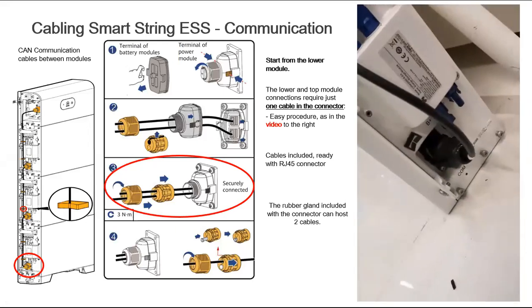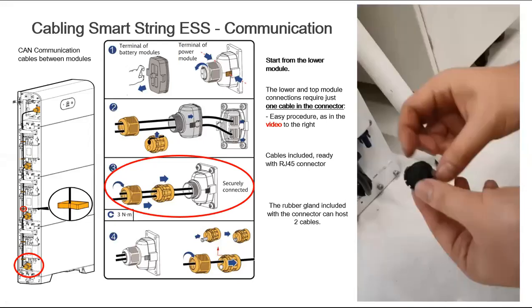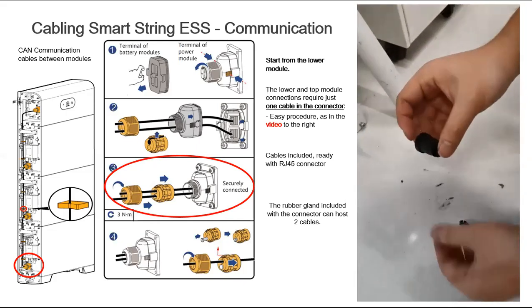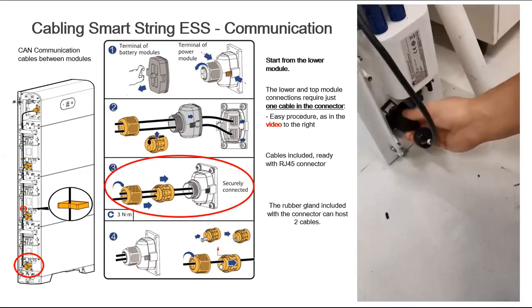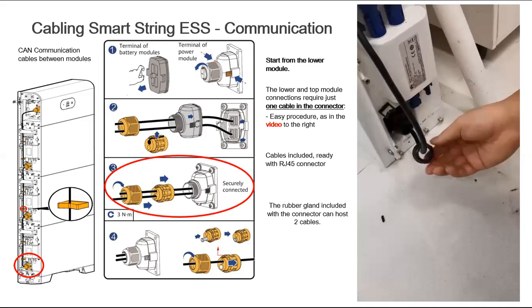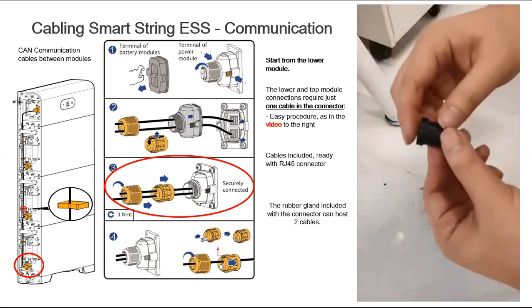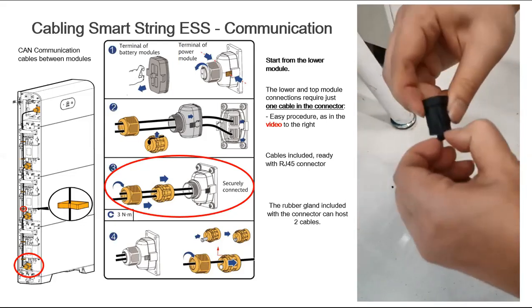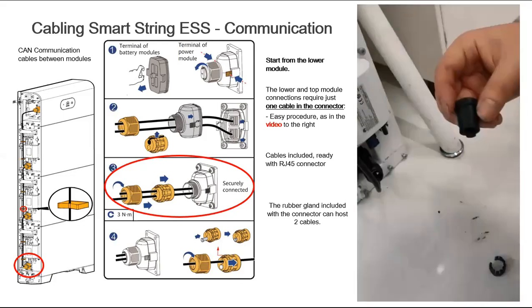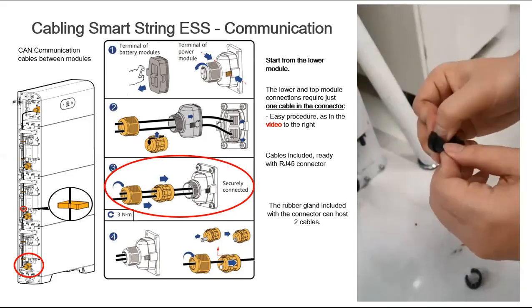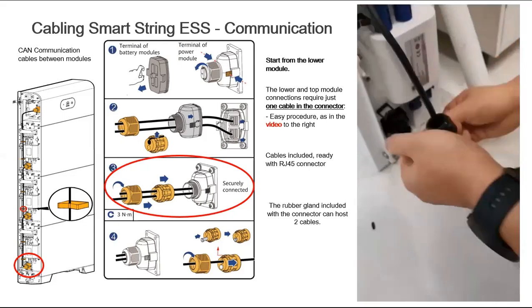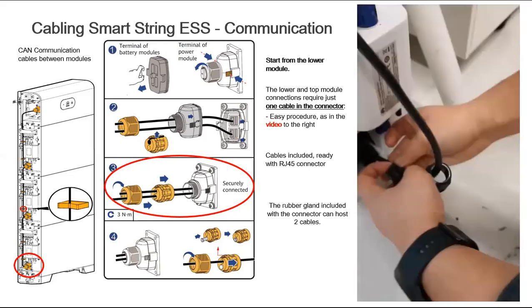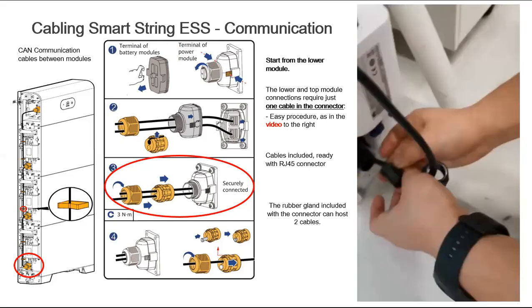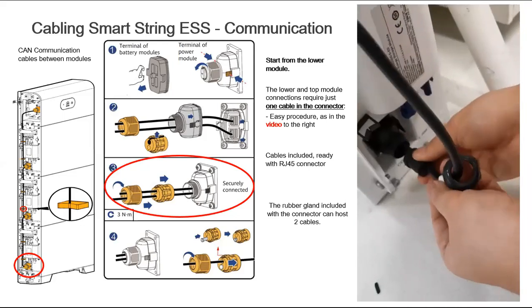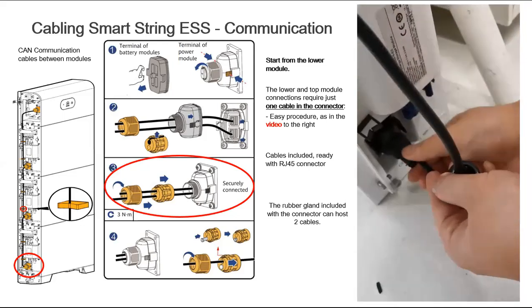And one more thing: for the last battery module and the top power module, you will only use one communication cable, but for the other battery modules, you will use two communication cables to communicate with the power control unit. You can always put the rubber gland there, so that it will be IP65 and no water can go inside the communication connectors.